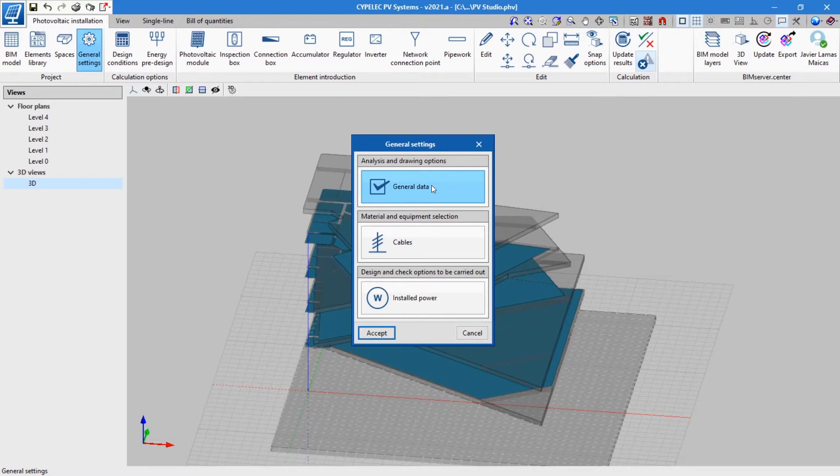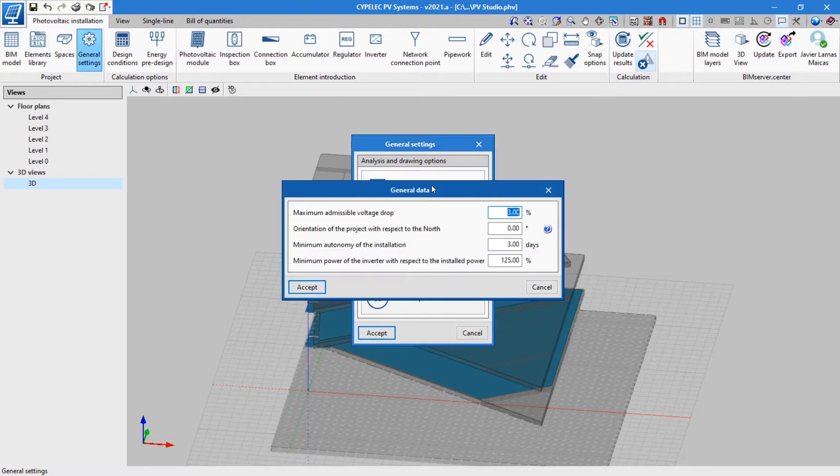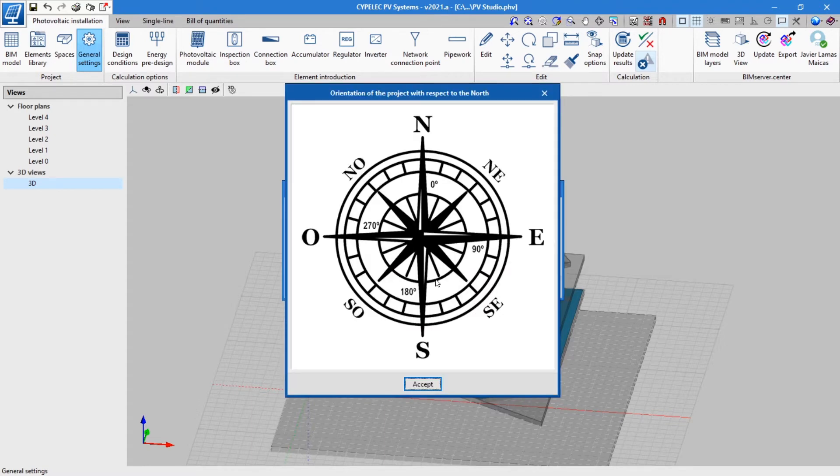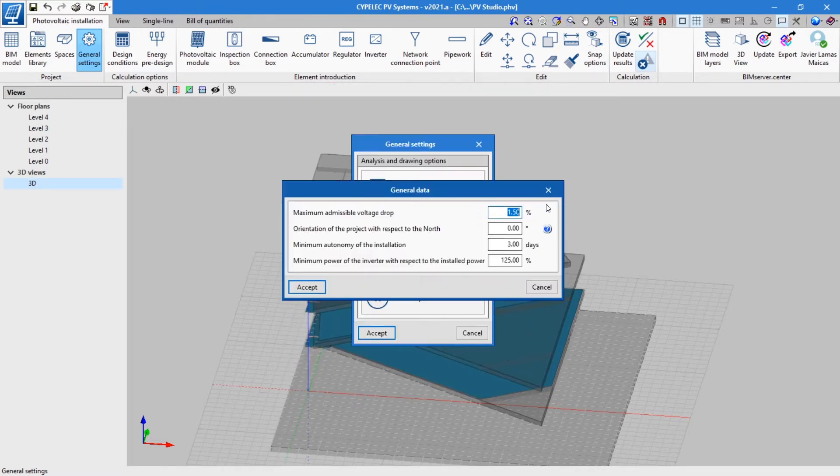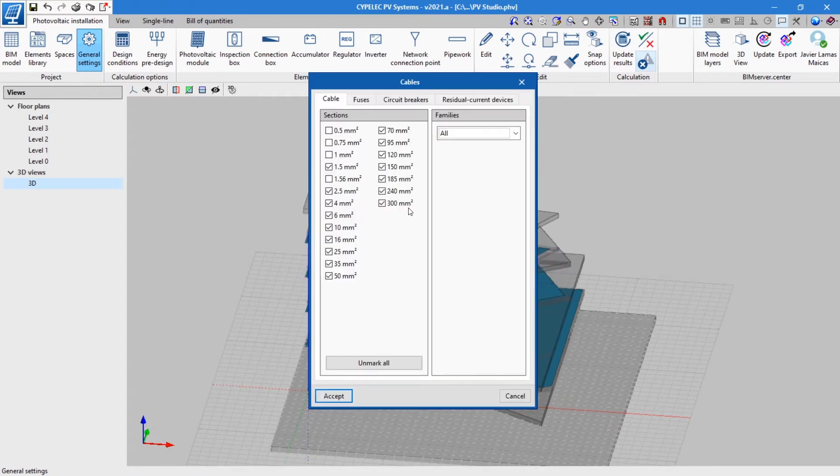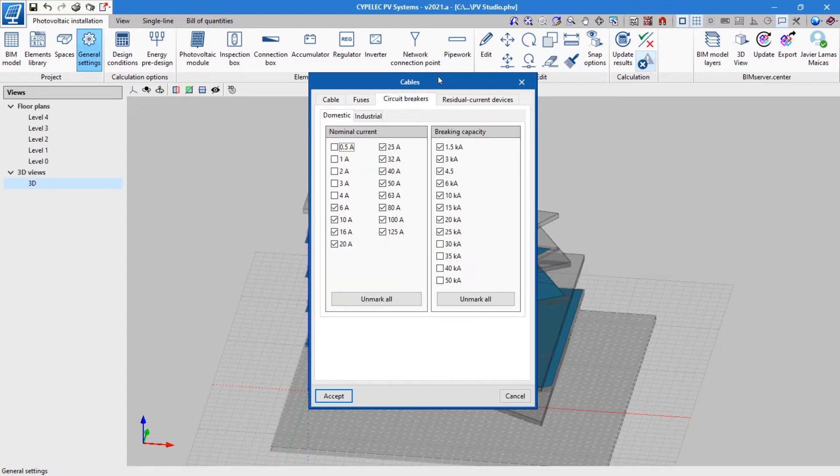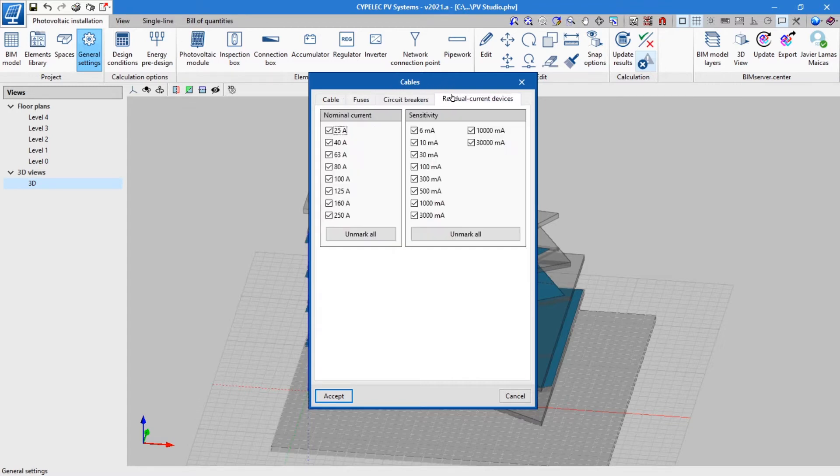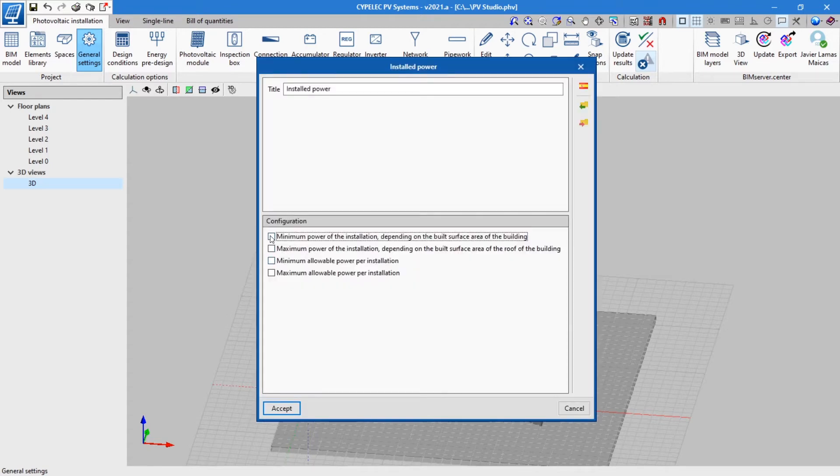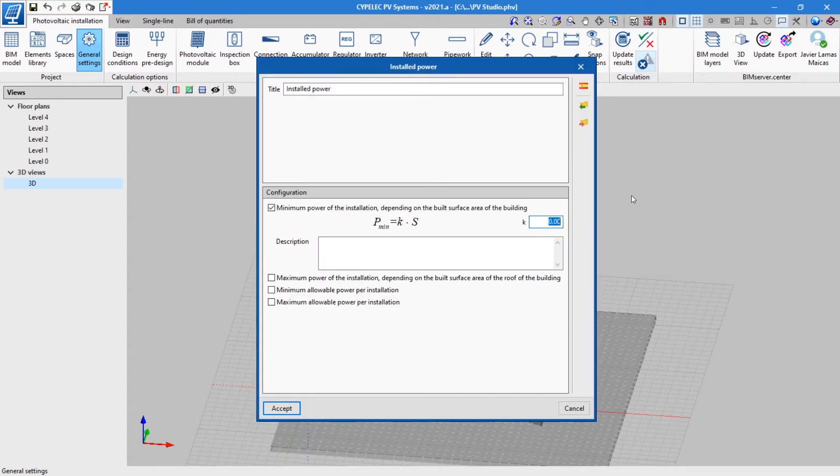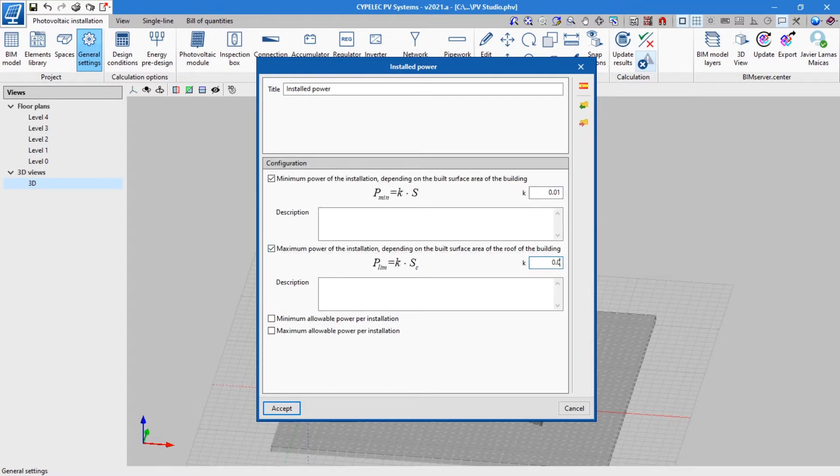In the General Settings tab, users can configure general data such as the maximum admissible voltage drop, orientation of the project with respect to the North, minimum autonomy of the installation, and minimum power of the inverter with respect to the installed power. It also allows users to select sections of cables and the diameters of the electrical protection elements available. Furthermore, the range of power can be determined either by entering them manually or by using the loaded standard specifications.